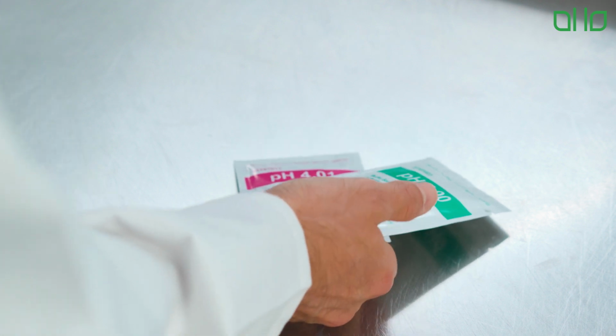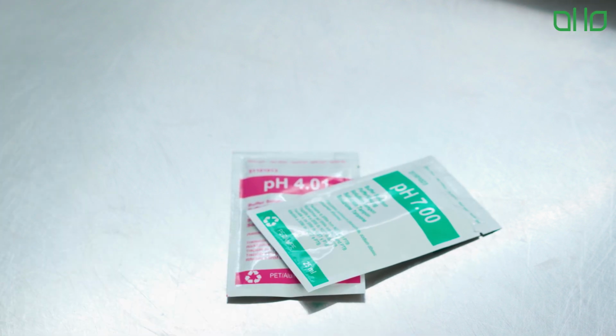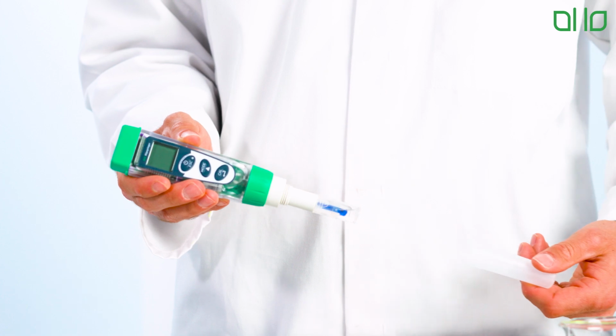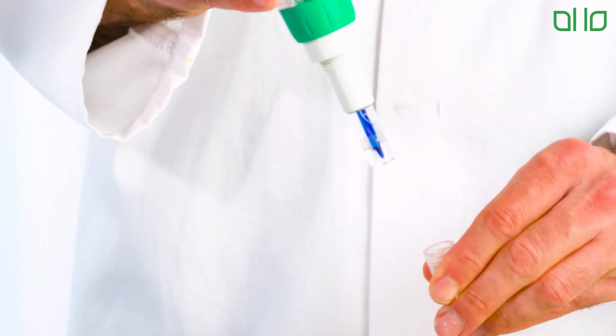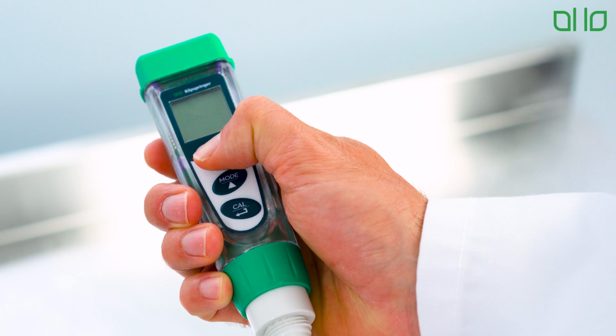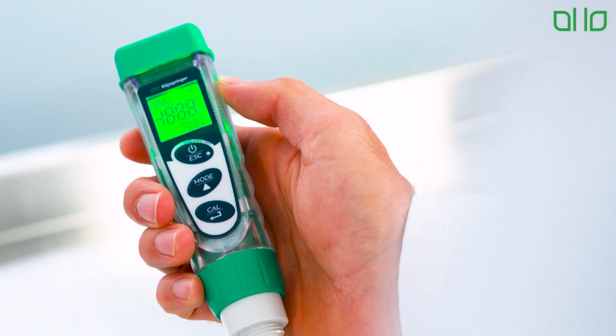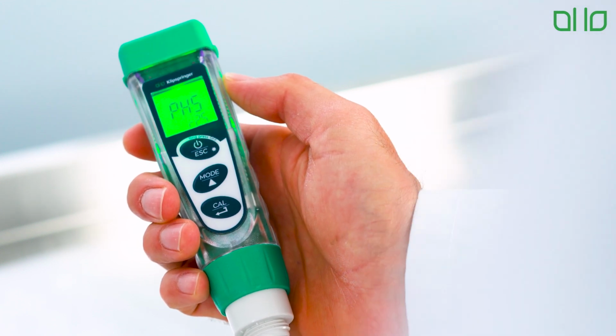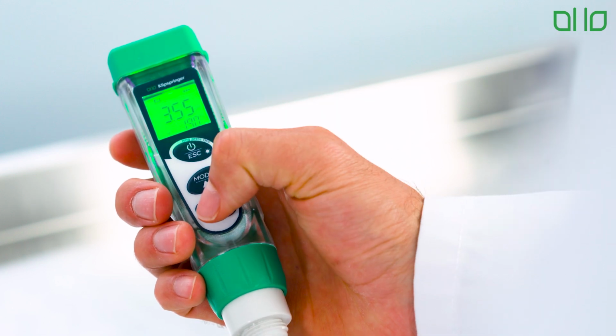Start by taking your pH meter and the correct buffer solutions, usually pH 7 and pH 4. Remove the cap containing the storage solution from the probe before switching on the device. Press the on-off button to turn on the meter. Switch the meter to calibration mode. You can navigate this on the front of the device.